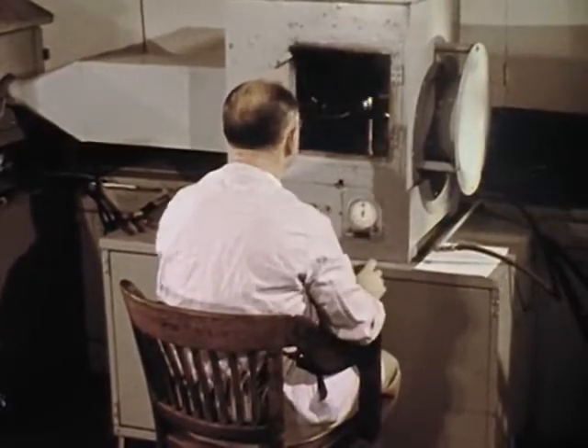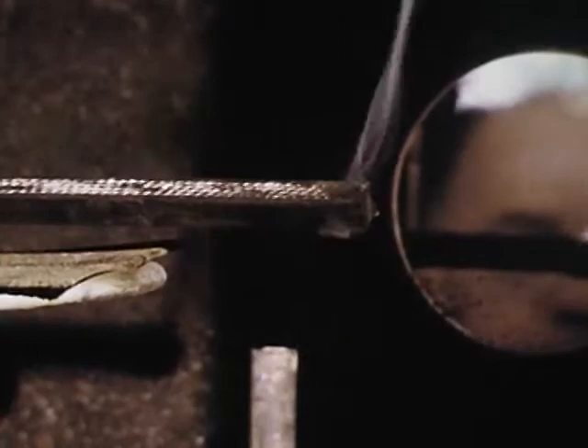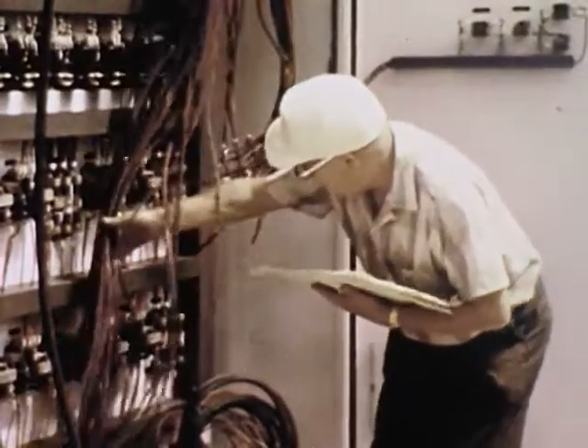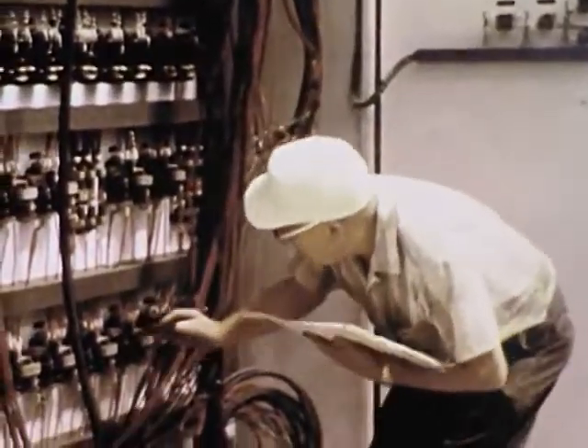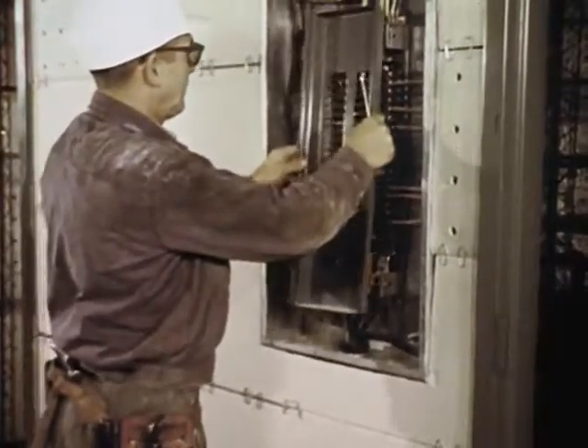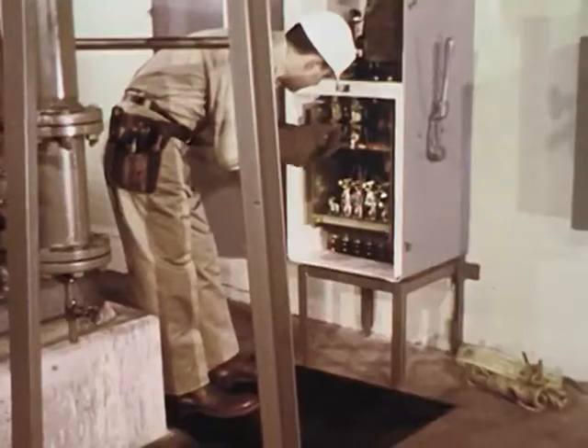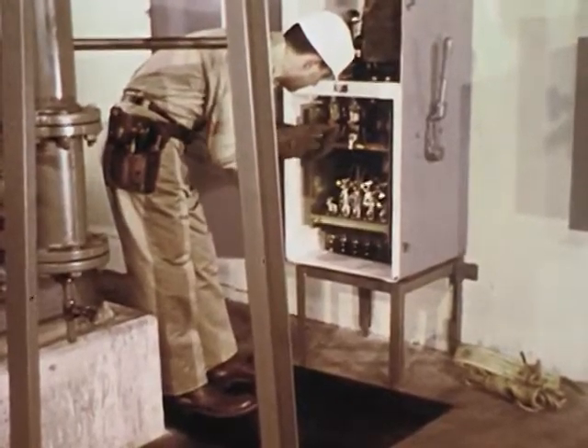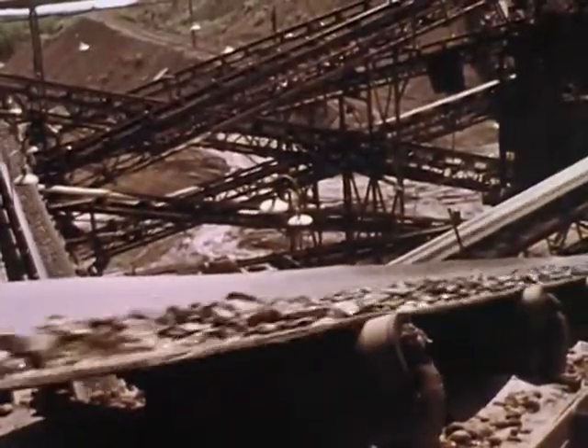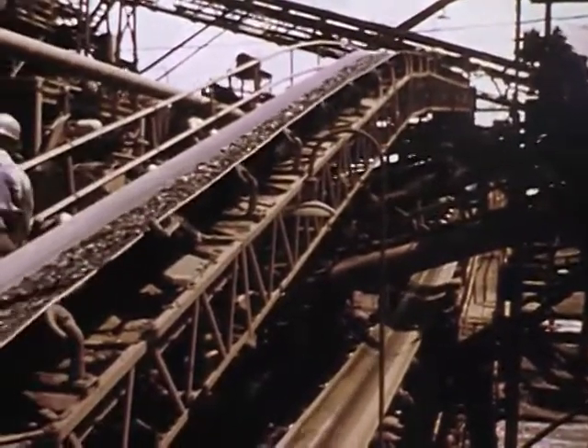To prevent belt fires, all belts should be fire resistant and the entire belt system carefully aligned. To prevent electrical breakdowns and overheating, the importance of first-class electrical installation — including properly rated switches, circuit breakers, resistors, and conductors — cannot be emphasized too strongly. When two or more belts are in series, automatic means is necessary to start and stop the belts in proper sequence.